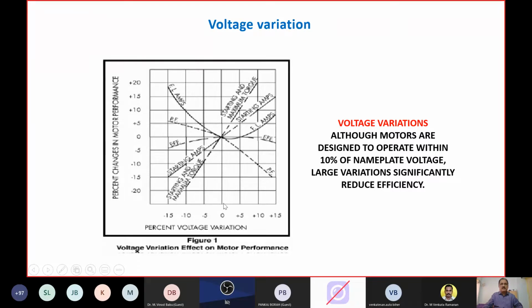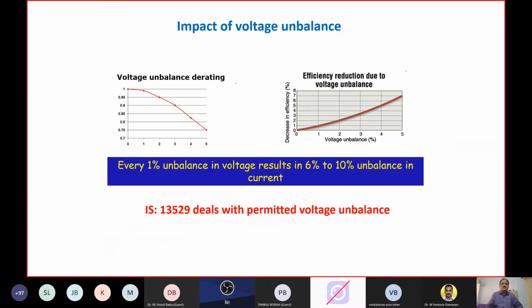So typically where you apply a new high efficiency motor like IE3 or IE4, you must ensure that the voltage variation is not like 10% or so. So this is a factor which needs to be understood by the industry people. They can't claim that I purchased IE3 or IE4, but I am not getting the energy saving. Voltage fluctuation or voltage variation is a very undesirable component when it comes to implementing energy efficiency.